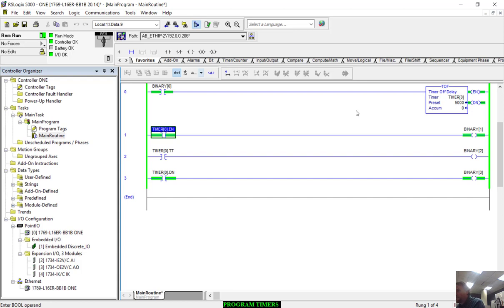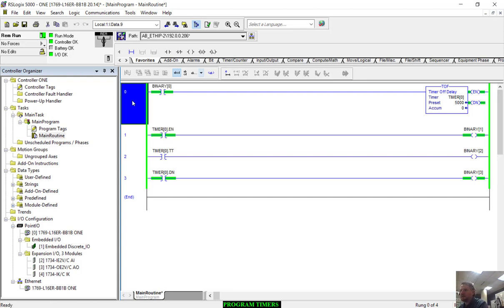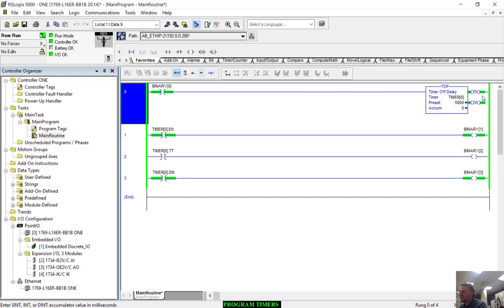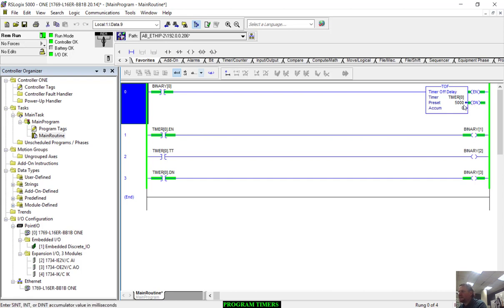Now let's watch this closely. I'm going to toggle this off. I'm going to hit control T to toggle binary zero off. Let's watch what happens immediately. The first thing that's going to happen is the enable is going to turn off because it's not enabled anymore. The done bit is going to stay on because it's not done timing yet, and the timer timing is going to turn on.